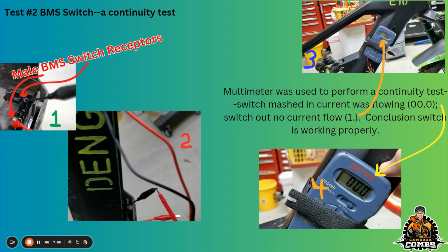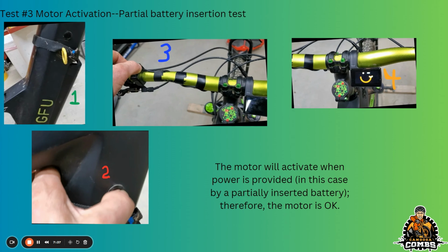Now, the fact that it changes from 1 to some other number means that once the switch is engaged, there's a continuous line, and because the continuity test indicates that there is continuity, you can conclude that the BMS switch is working properly. So the BMS switch is not the problem here.